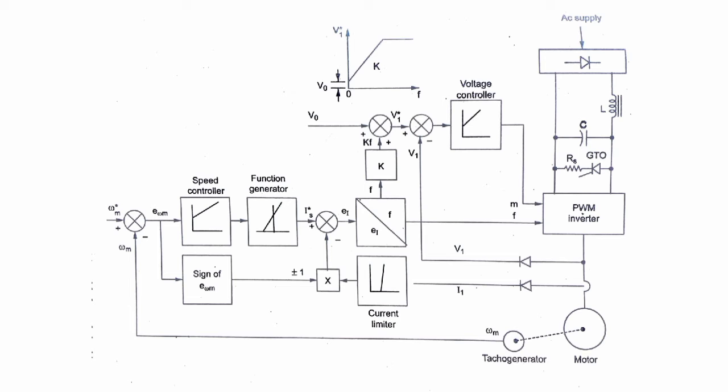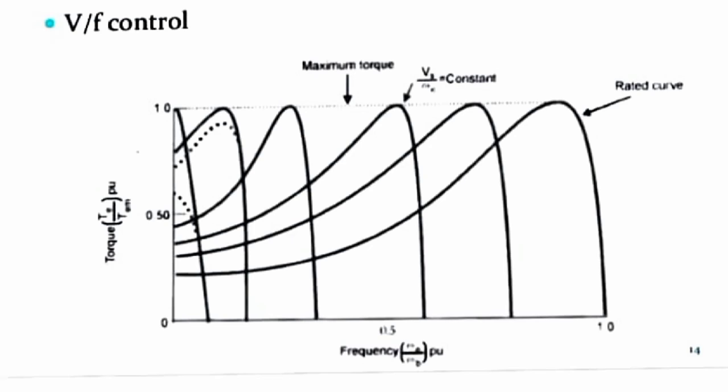A closed loop system is used where precise speed control is required, because even if any external disturbances happen, the closed loop system will identify it and maintain the desired rotor speed N* which we want. So the first step is to sense the actual rotor speed N using the speed sensor. The desired rotor speed N* can be given by any non-technical person. Both N* and N are compared in the error generator, which generates the error equal to N* minus N.